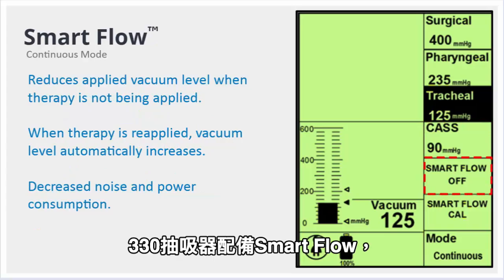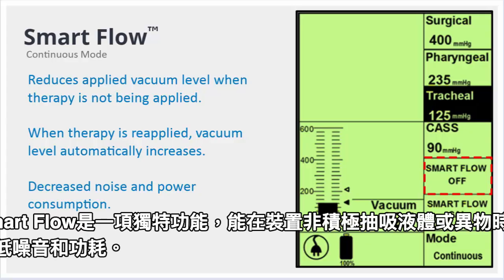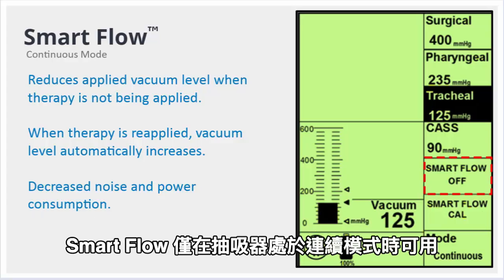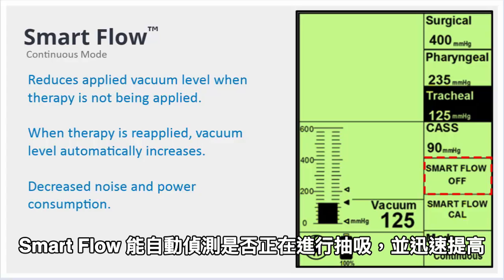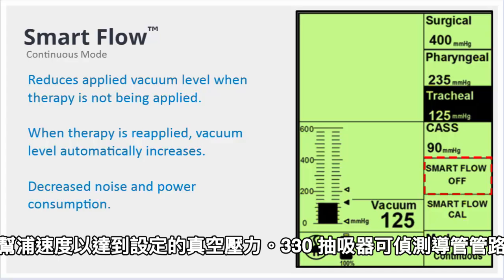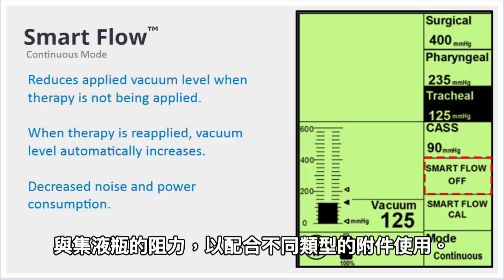The 330 is equipped with SmartFlow. SmartFlow is a unique feature that reduces the noise and power consumption when the device is not actively aspirating fluid or debris. SmartFlow is available only when the aspirator is operating in continuous mode. SmartFlow automatically detects when the suction is applied and quickly increases the pump speed to achieve the set vacuum level. The 330 can determine resistance of the catheter tubing and collection canister to accommodate various types of accessories.